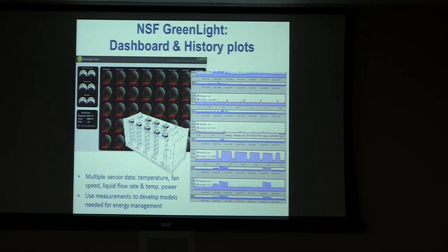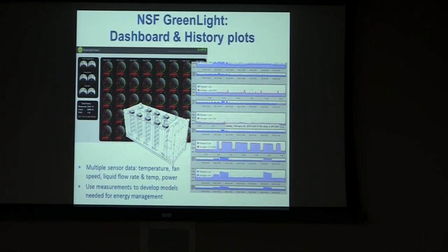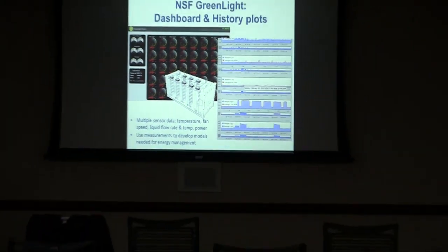You can use temperature sensors to in some sense decode power as well, but it's not as accurate because it's a strong function of what happens around the system. Temperature is really more of a low-pass filter—if there are hot servers nearby, or strange fan configurations like fans at the rack level in this container, that will strongly influence what temperature you see. So you either need to be aware of the configuration to adapt your power estimate, or use additional information. I honestly don't see a problem in adding power sensors in hardware—people just didn't need them before, so they didn't add them, and there's nothing difficult about calibrating a power performance counter post-production.